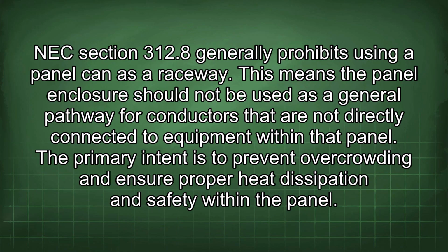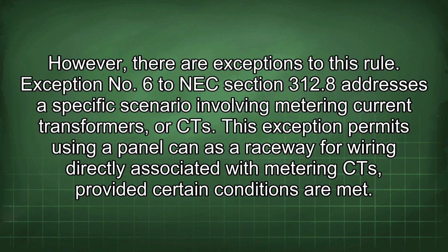NEC Section 312.8 generally prohibits using a panel can as a raceway. This means the panel enclosure should not be used as a general pathway for conductors that are not directly connected to equipment within that panel. The primary intent is to prevent overcrowding and ensure proper heat dissipation and safety within the panel. However, there are exceptions to this rule.